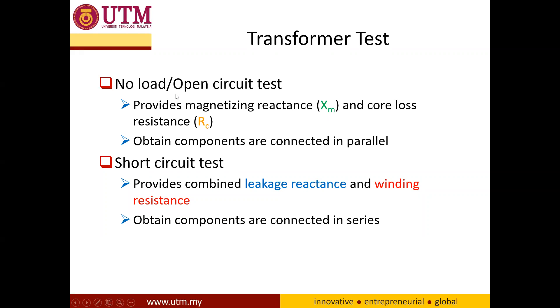In the open circuit test, the parameters that we obtain are the magnetizing reactance XM and the core loss resistance RC. While when conducting a short circuit test, the parameters that we obtain are the leakage reactance X and also the winding resistance R.